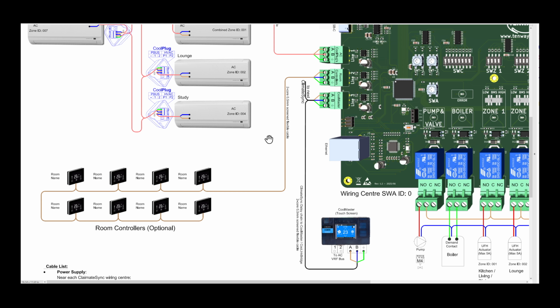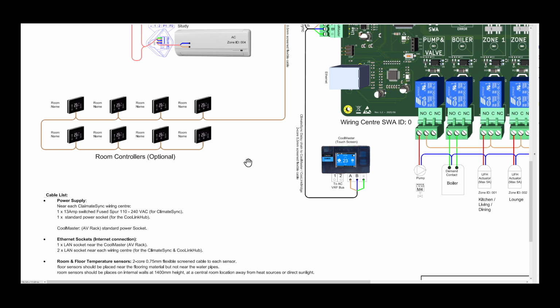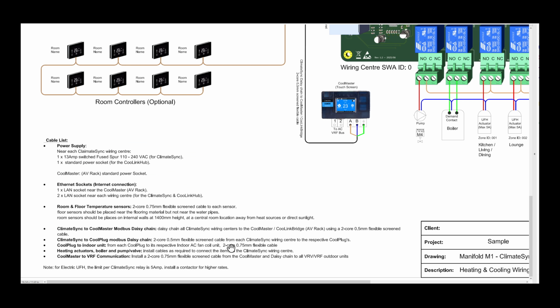If it is the budget controllers, then the power supply to all the controllers will be a high voltage supply. For Europe and the UK, that will be 220 to 240 volts. For the US, that will be 110 volts. That's for the budget controllers, and that will be in addition to the communication, the Modbus daisy chain that goes to those controllers. Here at the bottom of the wiring center diagram, you can see the different cable instructions.